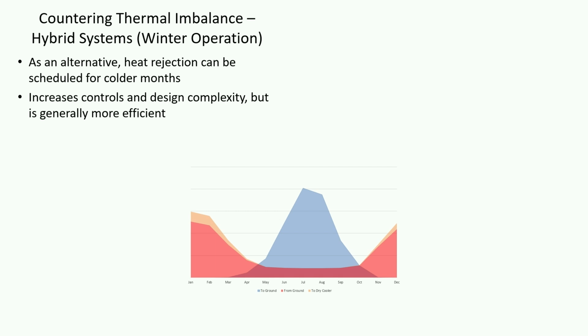And our third and final option that I'll discuss: you can take this hybrid system and not run it as a peak to meet your peaks. So we would then schedule, instead of on our hottest days of the year as our condenser water temperatures are rising, we actually balance our system in the colder months of the year, when it's more efficient to run a dry cooler or some other thermal resource to be able to reject this heat.